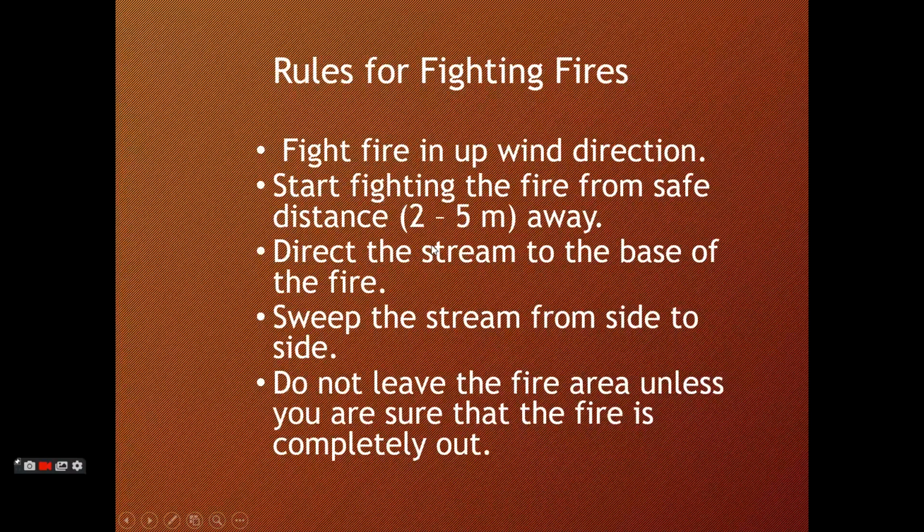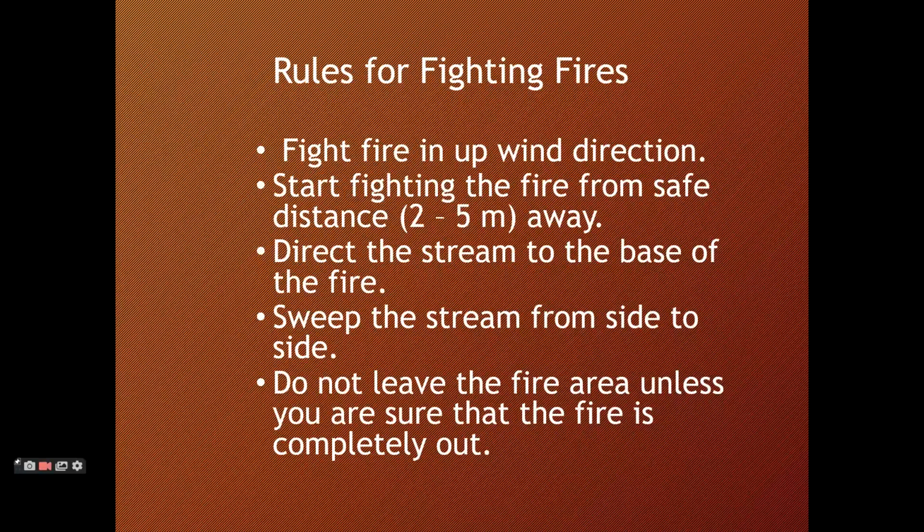Direct the extinguisher at the base of the fire. As I said, whenever you are extinguishing any fire, always aim at the base of the fire. After that, sweep the stream from side to side. Do not leave the fire area unless you are sure that the fire is completely out.